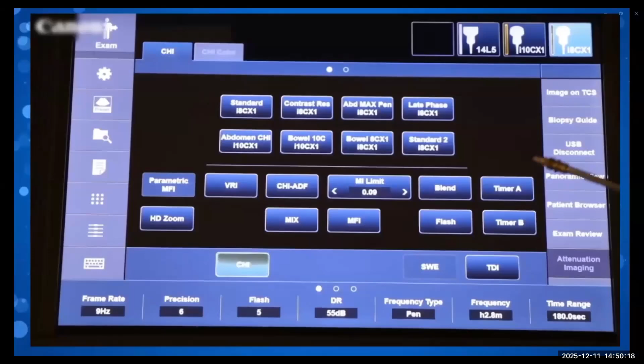Moving to our touch panel, before you start your contrast exam, you'll notice on the Canon Aplio i800, in the top right-hand corner, you have your contrast-capable probes. Just below this, you have your automatic presets. Here we have one for abdomen and contrast. If you press these presets, it will automatically select your probe. It's important to know for contrast where your software is to go into your dual screen display or your contrast software. It's also important to know where your timer lies to start your timer. And one of the most important features for any contrast exam is to know where your mechanical index limit is set. Here on the Canon Aplio i it is at 0.09. And of course, we can move and adjust this MI limit, which is essential to contrast exams.